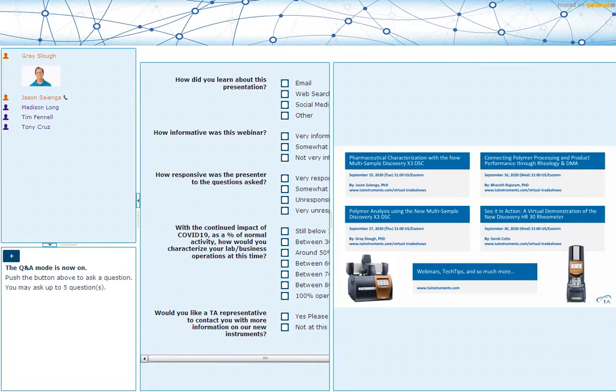First question is, do you have to run 3 samples at a time in this instrument? Certainly not. It's obviously designed to maximize the number of samples, but it can certainly be run as a single sample system if need be. The one great thing about the T0 sensor design is that each sensor is independent of one another, so you're not necessarily going to impact the performance of that sensor just because you're running 1, 2, or nothing on a particular sensor. So no, there's no reason why you can't run a single sample at any point in time.